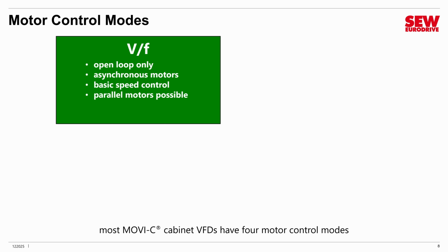The first is called VF mode. It's sometimes called volts per hertz mode by some people. It's a very simple mode. It is open loop only. You cannot use feedback even if you have an encoder. If you hook it up, it will just be ignored. It works only with asynchronous motors or induction motors. It provides basic speed control mode. You can run motors in parallel if they're very close in size. This is really just a very bare bones mode. It's good if you're just running an asynchronous motor and you don't care too much about precision, or if you're trying to get a third-party motor working, this is a good place to start.